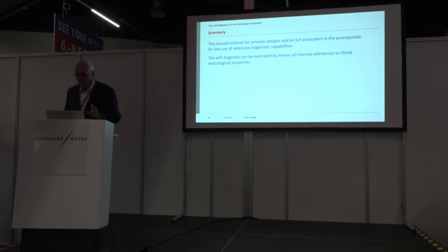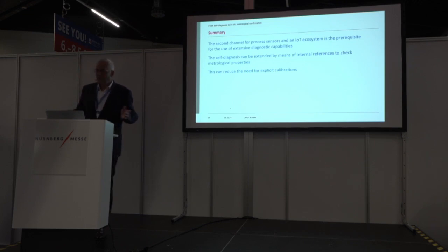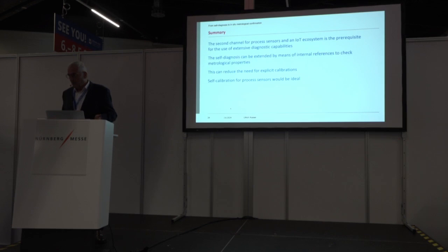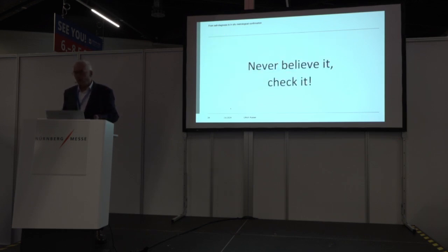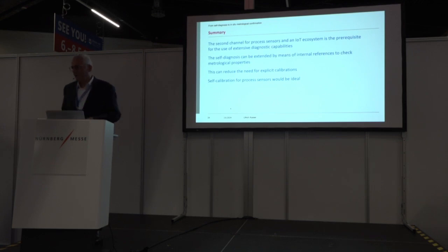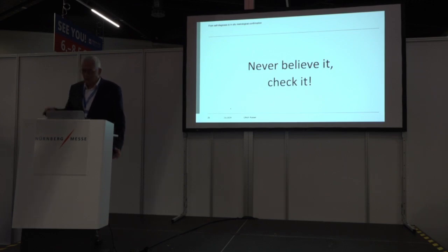The self-diagnostic functions which are now available can be extended by means of internal reference to check metrological properties, not only function. And this can reduce, not eliminate, the need for explicit calibration. Self-calibration for process sensors would be ideal, but it's not available. Maybe in the future, with NIST on a chip, we might have the possibility of full self-calibration, but this is still in the future. I don't know whether I will survive it. Last, never believe it, check it, and thank you for your attention.